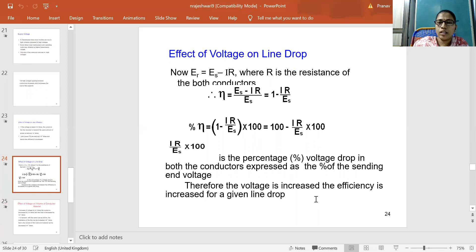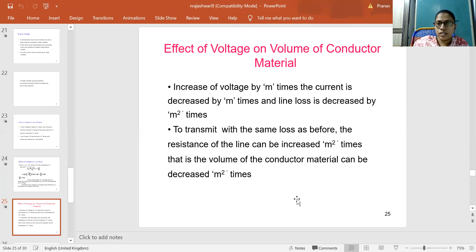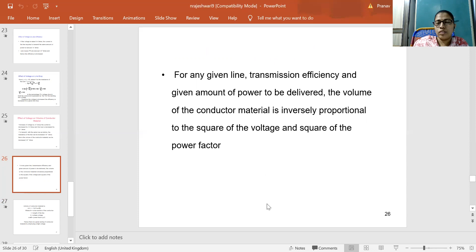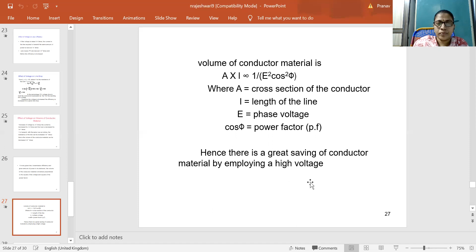And coming to the volume of conductor material, as we increase the voltage, the line loss decreases. And to transmit with the same loss, the resistance of the line is increased and the overall volume of the conductor is decreased. So for a given line transmission efficiency, the volume of conductor material is inversely proportional to the square of voltage and the square of the power factor, as given by this equation. Area of cross section times length of the conductor gives the volume of the conducting material, which is proportional to 1 by E square cos square phi. E is the voltage and cos phi is the power factor. So it is inversely proportional to E square and cos square phi. So by taking high voltages, we will save conductor material, copper, with the high voltages.